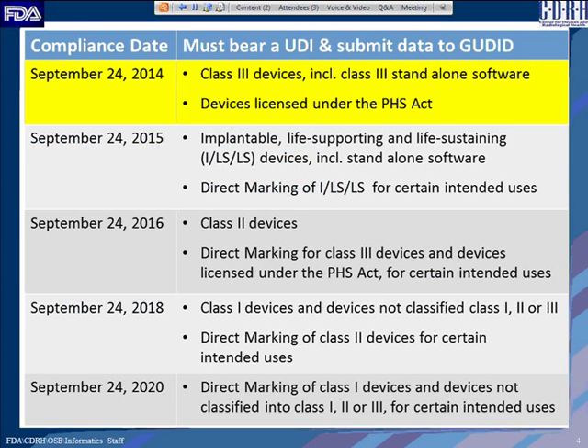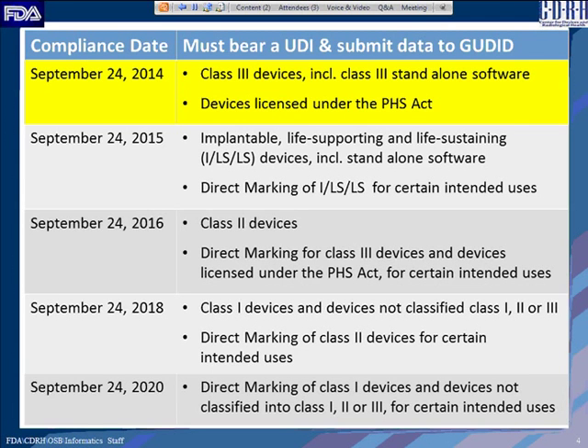A quick overview on compliance dates: the dates are all September 24th, running through 2016, 2018, and 2020. On the right-hand column we show the class of device that must have a UDI on the label and the data that must be submitted to GUDID. The immediate focus right now is on class three devices and devices licensed under the Public Health Act, which must be submitted to GUDID by September 24th and must have a UDI on the label.